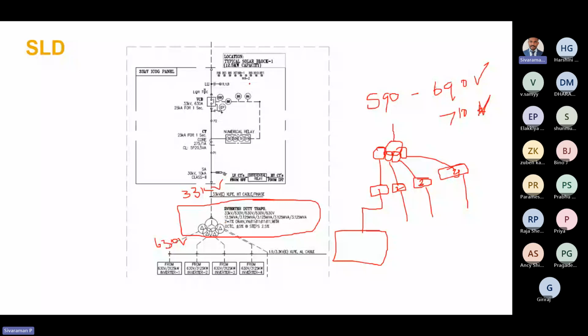Okay, so in this example, what you are seeing is 12.5 MVA. This transformer primary winding is 12.5 MVA. So each LV winding is 3.125 MVA. Each inverter is rated for 3.125 MVA. Okay, so the combined capacity is 12.5 MVA. The transformer impedance is 7%. It is ONAN, oil natural, air natural.